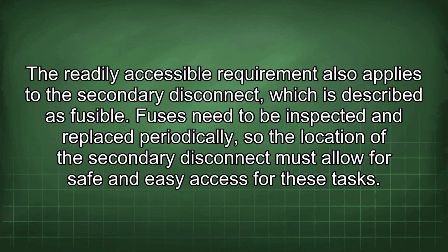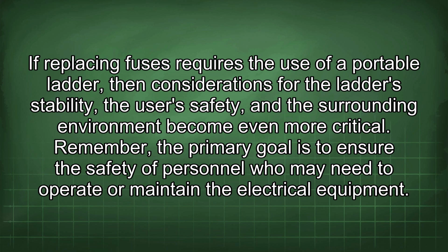The readily accessible requirement also applies to the secondary disconnect, which is described as fusible. Fuses need to be inspected and replaced periodically, so the location of the secondary disconnect must allow for safe and easy access for these tasks. If replacing fuses requires the use of a portable ladder, then considerations for the ladder's stability, the user's safety, and the surrounding environment become even more critical.